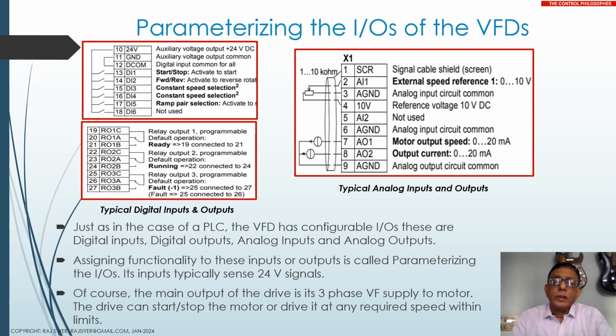Also the relay outputs are usually used for lighting up indicator lamps, such as for the trip condition, or to indicate with a green light that the motor is running. So you have to configure the relay outputs and wire these relay outputs into the control circuit of the panel. Of course, the VF pattern parameters are the other important thing.